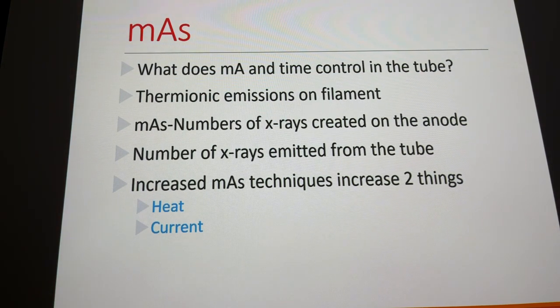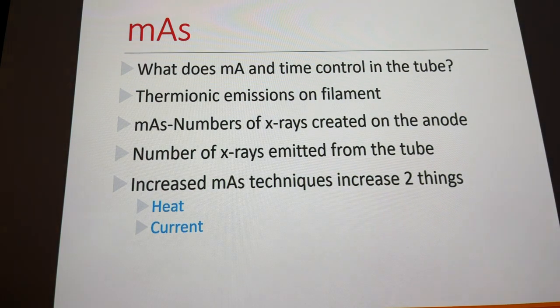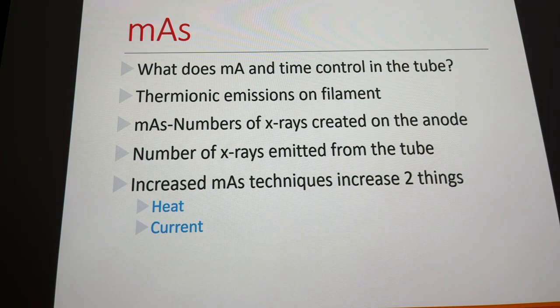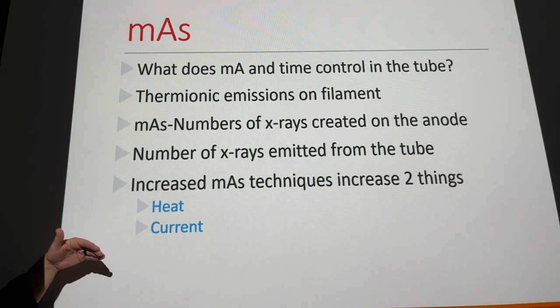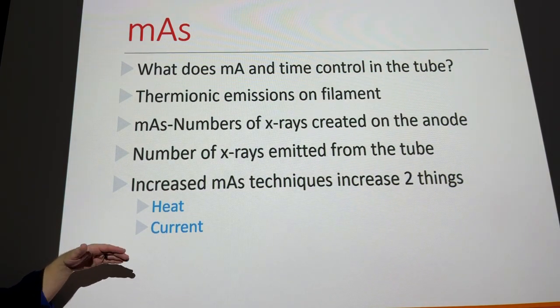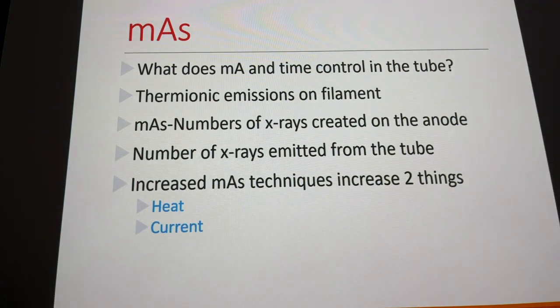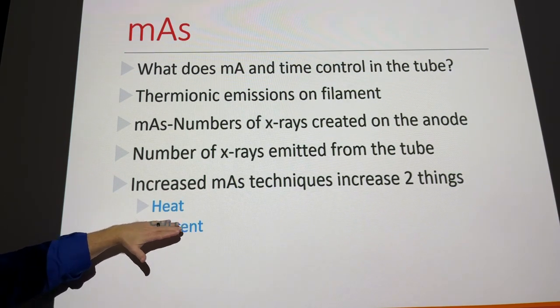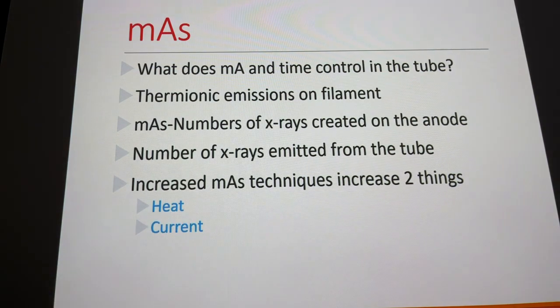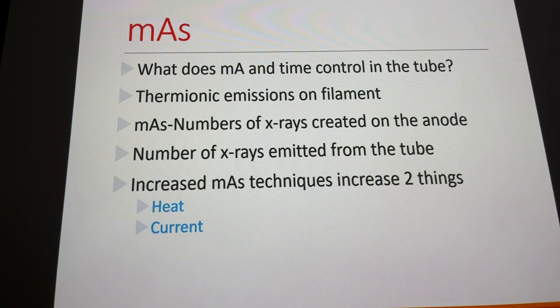The technical factor of choice expected to change in the future is KVP. As KVP goes up, we can decrease MAS, and patient exposure goes down — and in the X-ray tube, decreasing MAS decreases heat, so the tube lasts longer. Increasing KVP is better for the patient and better for the X-ray tube.